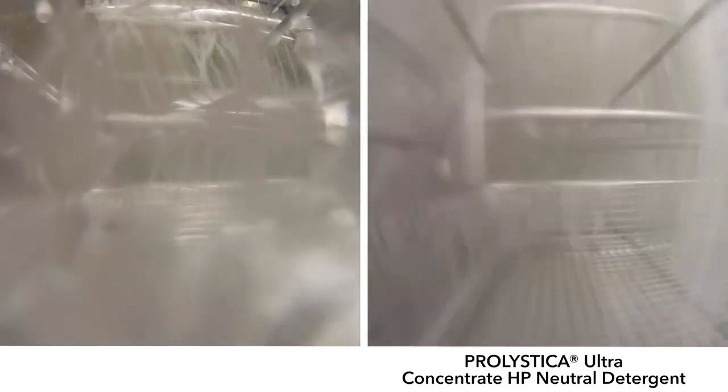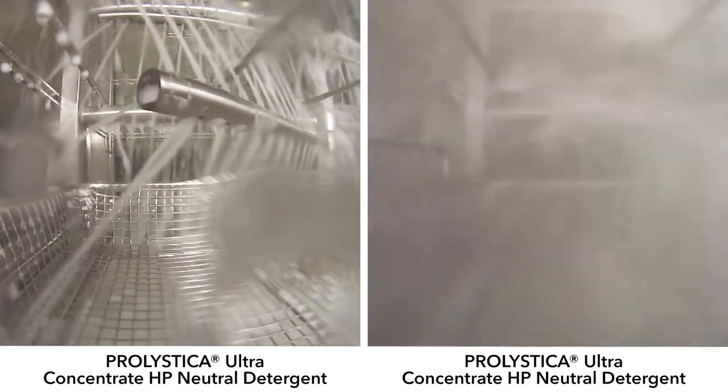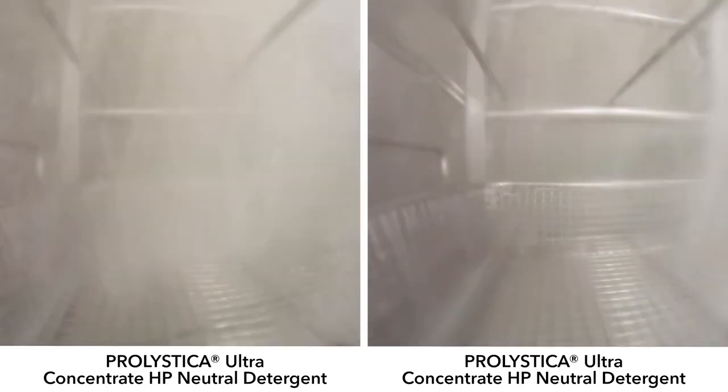Let's take this a step further. We've added Prolystica Ultra Concentrate HP neutral detergent to the washer with excessive foam and stopped spray arms. You can see the defoaming capabilities of Prolystica in action, where in seconds the foam is breaking and is then eliminated. The washer then returns to complete the cycle.